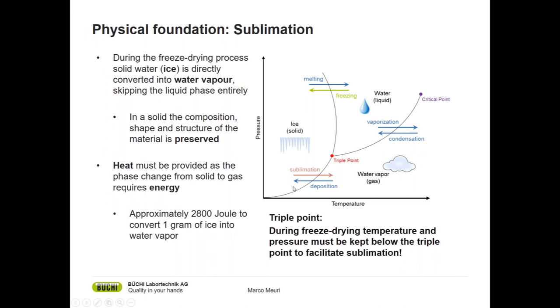The opposite process is called deposition, which is important in the condenser of a freeze dryer. To achieve sublimation, conditions need to be below the triple point of water, shown in red in the diagram. This is the point where water is available as ice, liquid, and gas at the same time. The conditions for water are zero degrees and 6.11 millibars of pressure. During freeze drying, we keep both temperature and pressure below the triple point — below zero degrees and below 6.11 millibar — and then sublimation will happen.